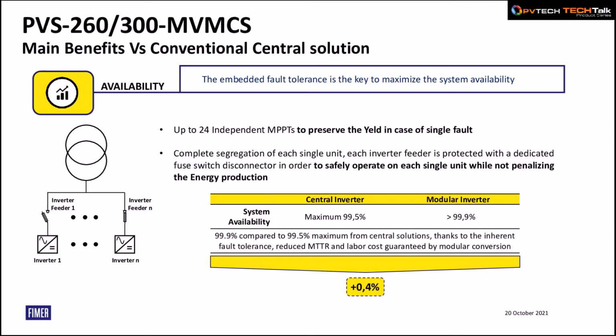Last but not least, it's also important that with this system you can effectively keep the full system live and just tackle the single point of failure, while with a central inverter you have to completely keep the system off in order to repair or replace the failed parts. This in general is converted into availability. Availability of central inverters is maximum 99.5, while with our modular inverter we can exceed 99.9, and this is converted into a 0.4% improvement.